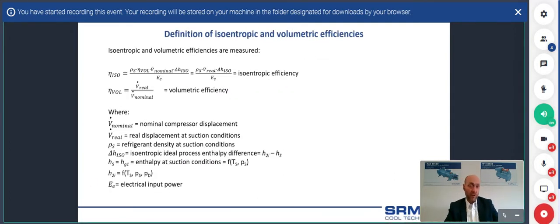In the evaluation of the efficiency of the compressor and so of the system, we have to mention two efficiency factors that we normally use. So the first one is the isentropic efficiency. That is the ratio between the suction density multiplied by the real displacement multiplied by the isentropic enthalpy difference between the discharge and the suction levels through an isentropic process, divided by the electrical input. The second one is the volumetric efficiency, that indicates how close the real displacement is to the nominal displacement. So of course, if it's not clear, you will have this publication later, so you can see also these parameters clearly indicated.